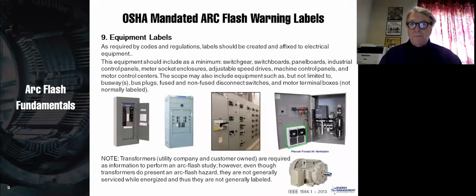Now, labels. This is out of now IEEE 1584. The labels must be on switchgear, switchboards, panel boards, industrial control panels, meter socket enclosures, adjustable speed drives, machine control panels, and motor control centers. So those are not optional. All of those things you must have labels on.